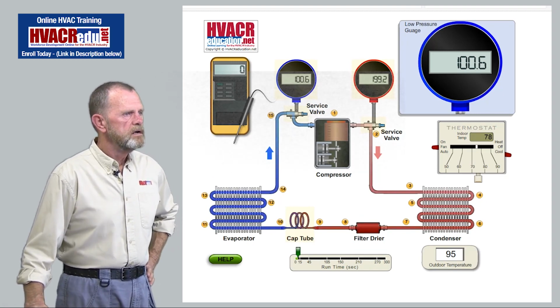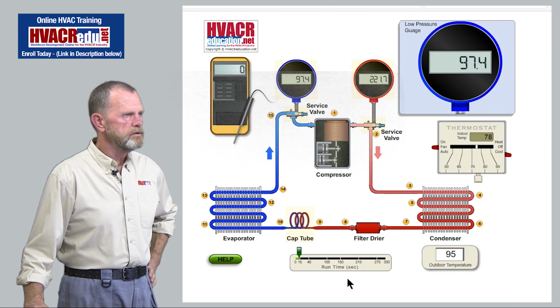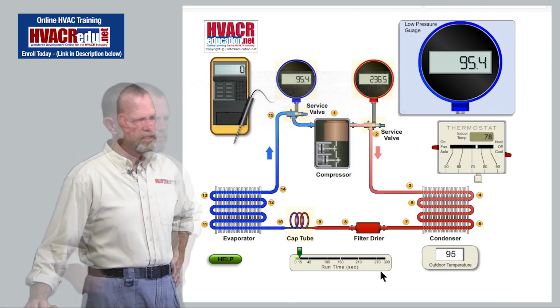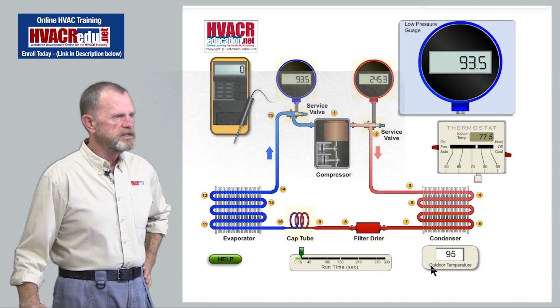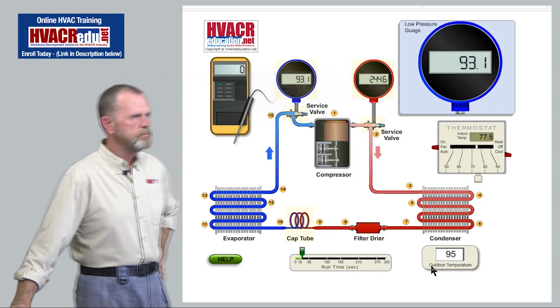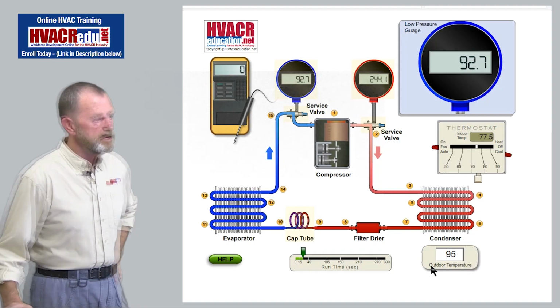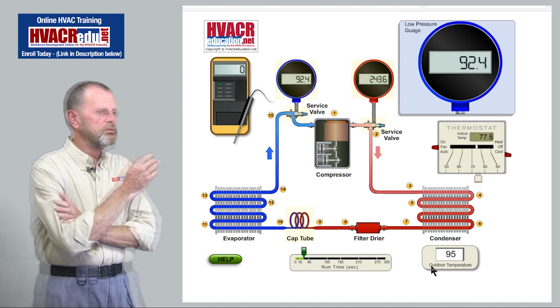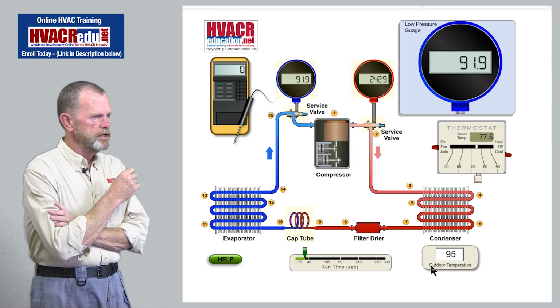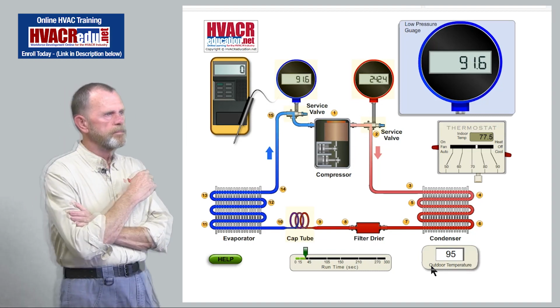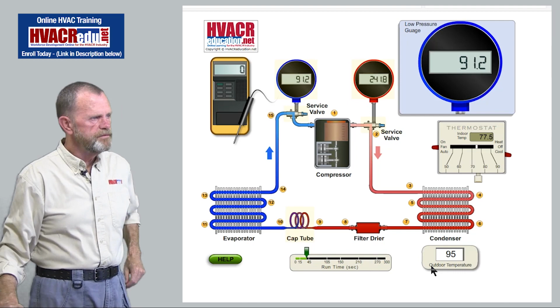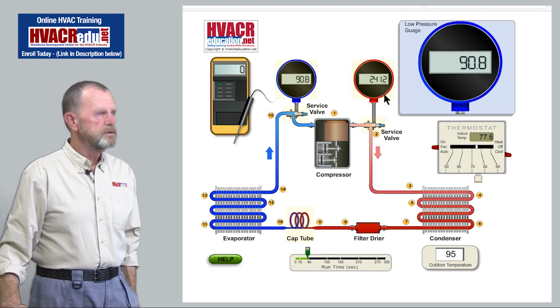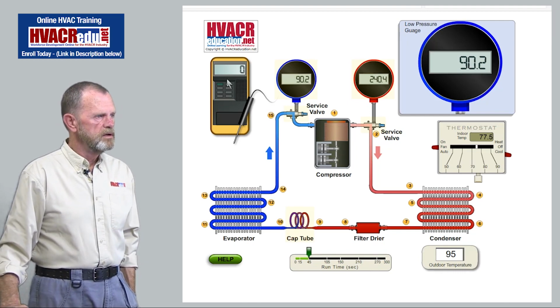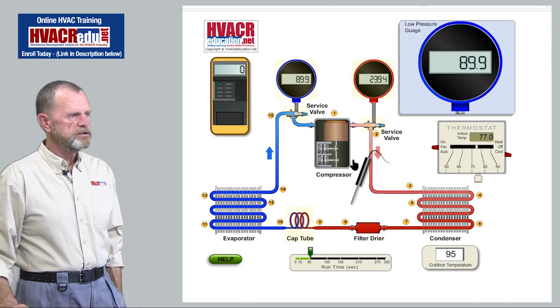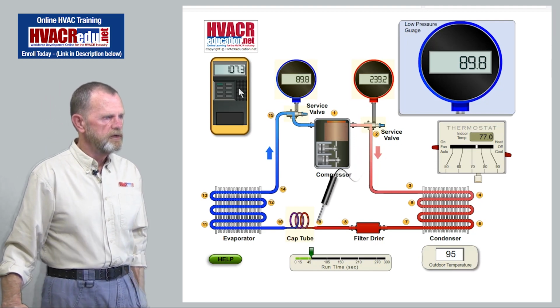And you can see down below here we have a runtime counter. It starts at 0 and goes up to 300 seconds. That's a 5-minute run. This is specifying that the outdoor temperature is 95-degree ambient, which is the rating point for unitary air conditioning products. AHRI rates air conditioning equipment at a 95-degree ambient. So I just threw that in there to give us a standard. Another feature is we've got an electronic thermometer with a temperature probe. You can take that temperature probe and move it around and measure temperature on the electronic thermometer. You can see the temperature changing up here and so on.